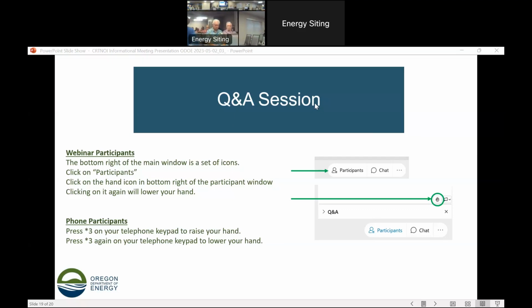My name is Gary Kuntz. I'm curious, can this project operate with either the DC negative or DC positive pole out of service, where you might have a ground return, and does that cause magnetic field problems? This project will only operate with two cables in service. The neutral is handled at each converter. There is no common return for the plus and minus cables, and no ground return either — that's dealt with in the converter design.